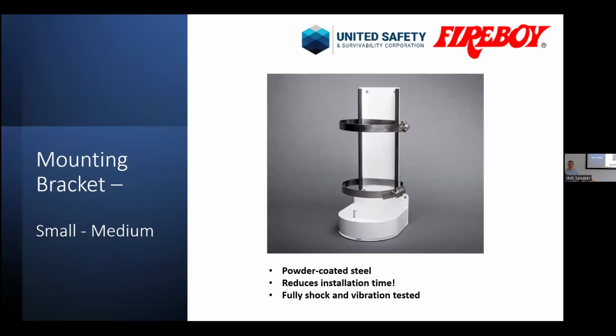Every single cylinder comes with a mounting bracket, a fitting bracket that we manufacture that's got proper vibe and shock testing. We've seen brackets that are secondhand or, you know, fit yourself because it didn't fit into the space, especially on the replacement jobs. So it's a retrofit, you know, older boat. So it's very important to fit the correct bracket because those are pressurized cylinders, and when they come off and they're not strapped properly, mounted properly, they could fall off or just, you know, come off and not do the job.